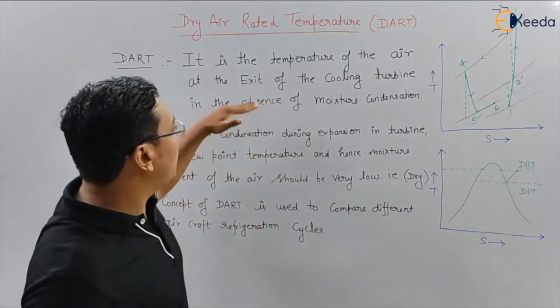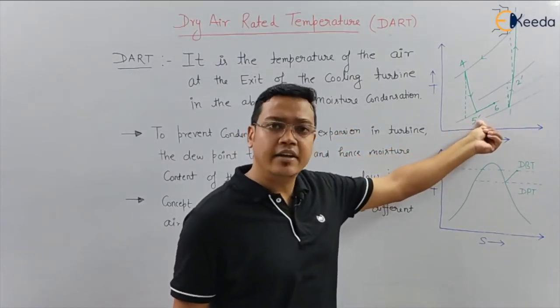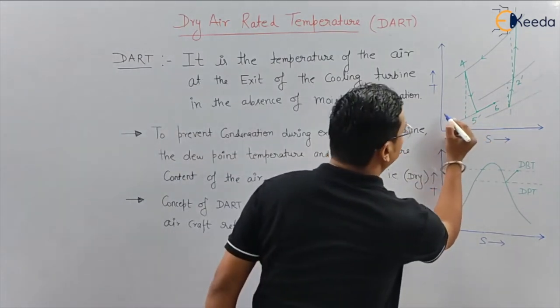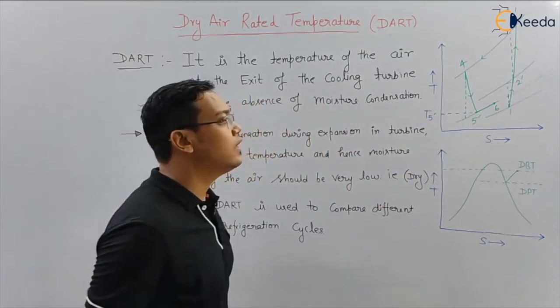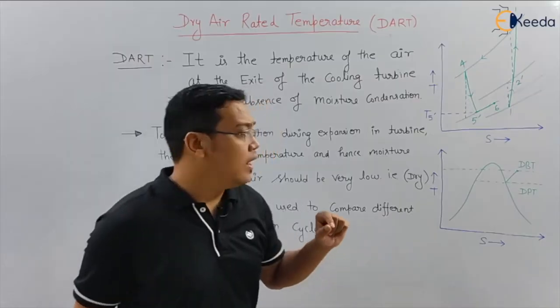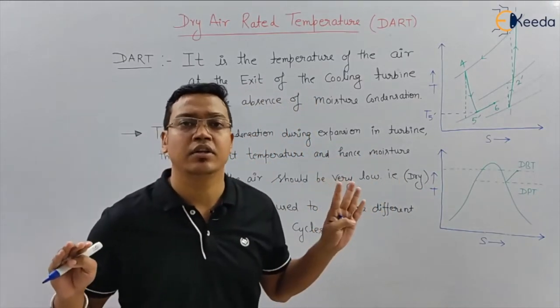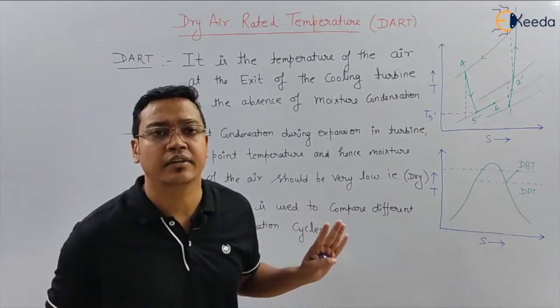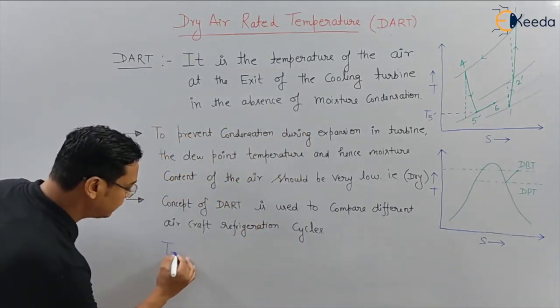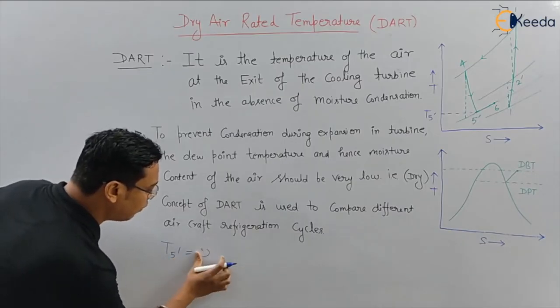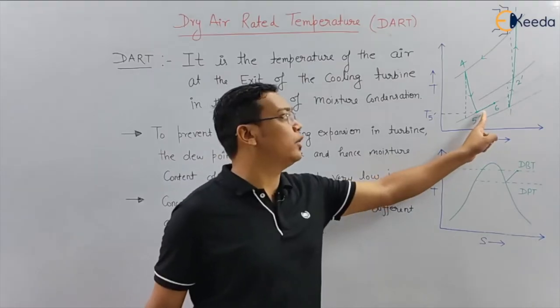From this definition you can easily identify that 5-dash is the exit of the cooling turbine. The temperature at this exit point is T 5-dash. According to the definition of DART, at this point there should be no moisture content. If there is no moisture content at point 5-dash, then the temperature T 5-dash will be the DART, also written as T_dart.